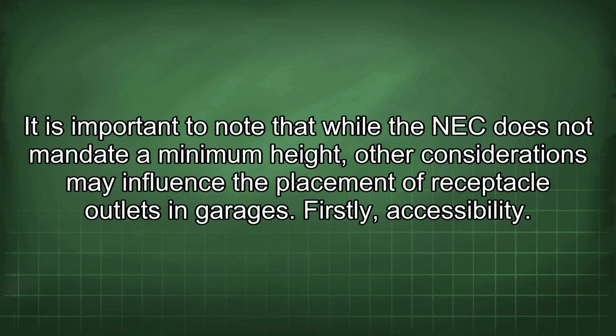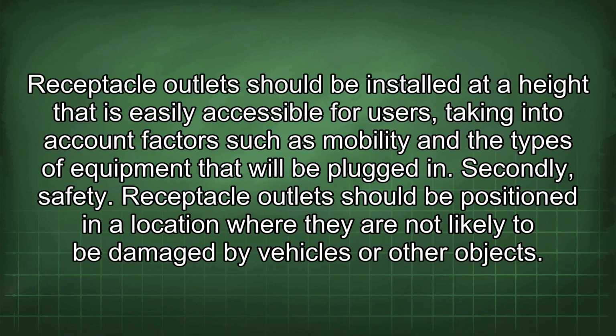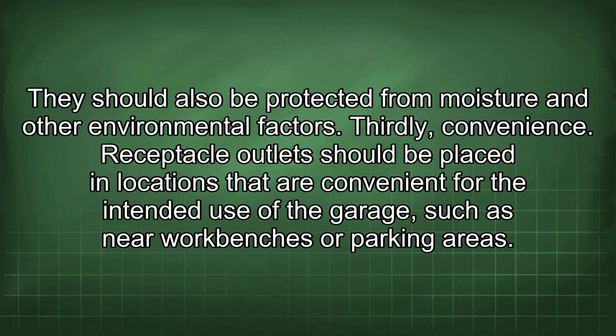Firstly, accessibility. Receptacle outlets should be installed at a height that is easily accessible for users, taking into account factors such as mobility and the types of equipment that will be plugged in. Secondly, safety. Receptacle outlets should be positioned in a location where they are not likely to be damaged by vehicles or other objects. They should also be protected from moisture and other environmental factors. Thirdly, convenience. Receptacle outlets should be placed in locations that are convenient for the intended use of the garage, such as near workbenches or parking areas.